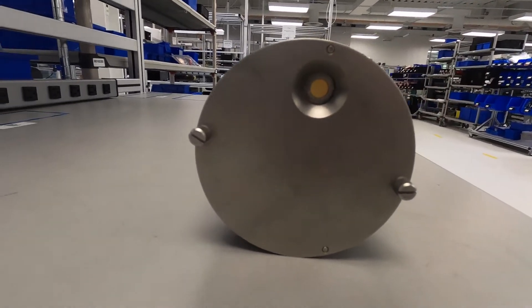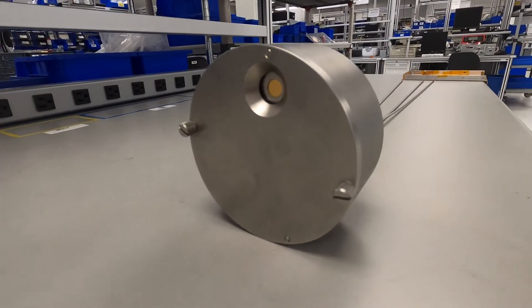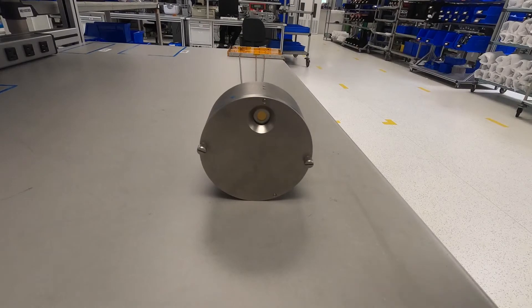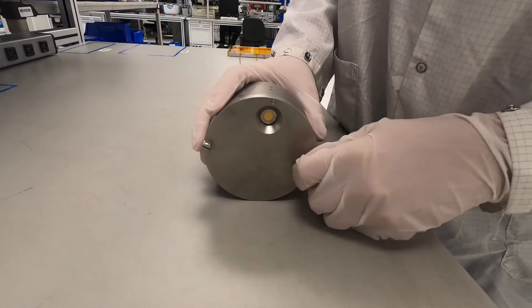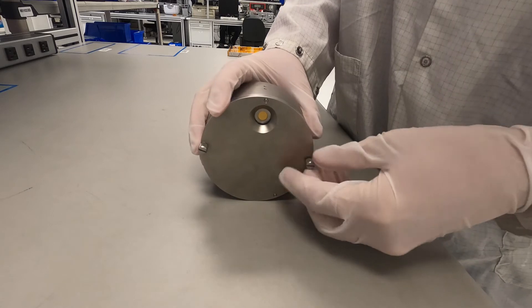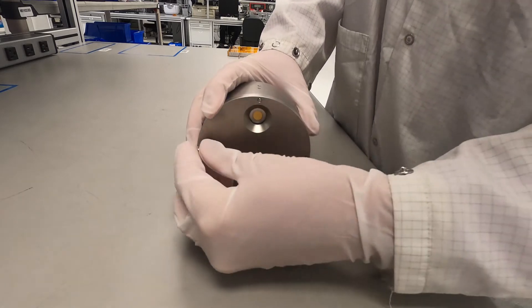To replace the crystals in the Crystal 12, you'll need to start by removing the front deposition shield to access the crystal carousel. The front deposition shield is secured by two fasteners to the carousel housing and will need to be removed.